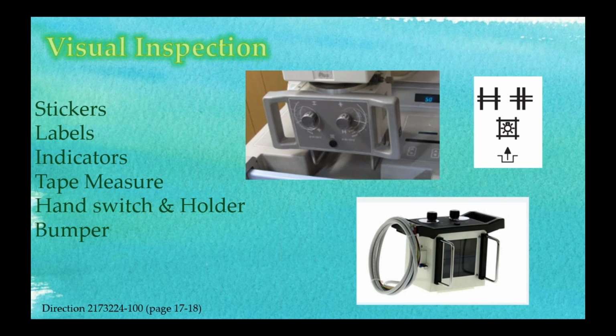Visual inspection, I'm checking labels, stickers, indicators. Collimator has a tape measure. Oh, look there. Inspector Gadget or whatever his name is. A couple things on the collimator that I need to mention: there are dials on the front of the collimator with numbers on them, but the numbers really don't mean anything to anybody except the physicist who's coming in to check it annually right behind me.